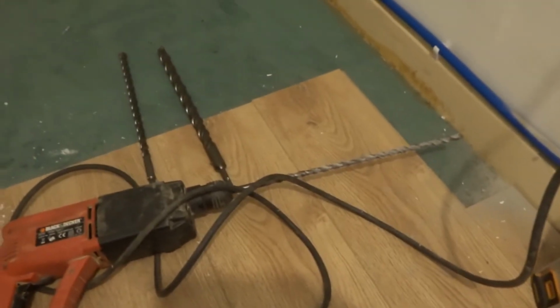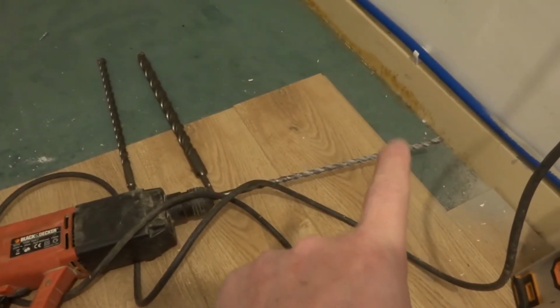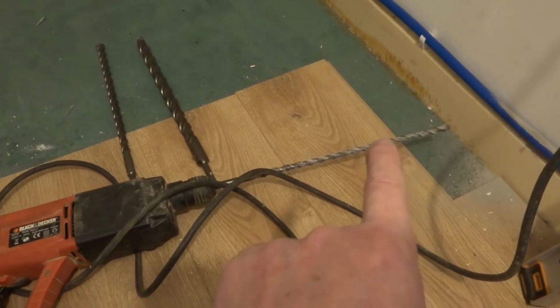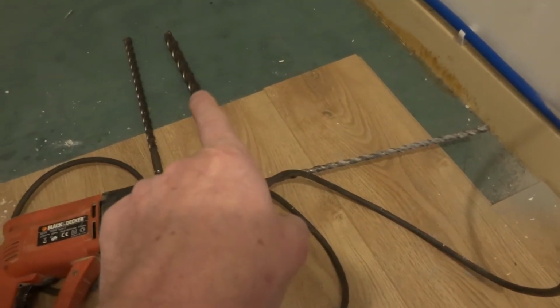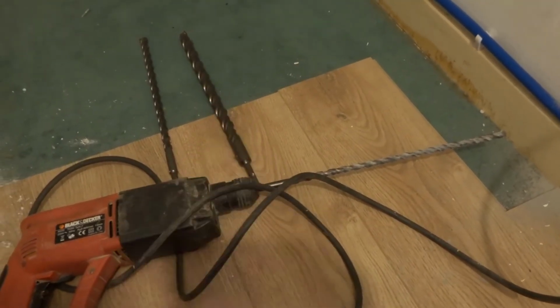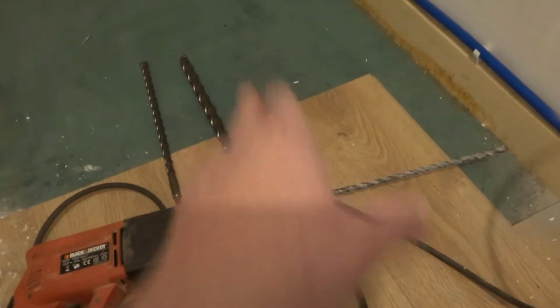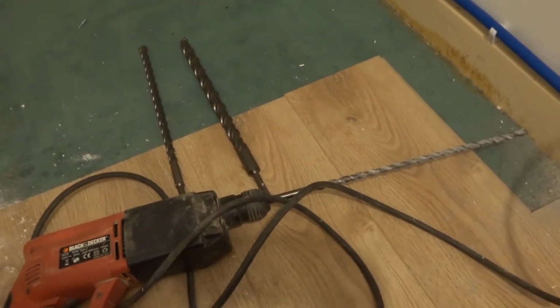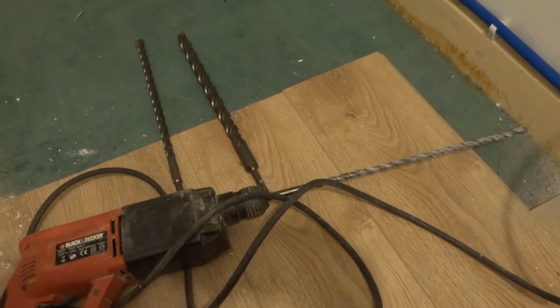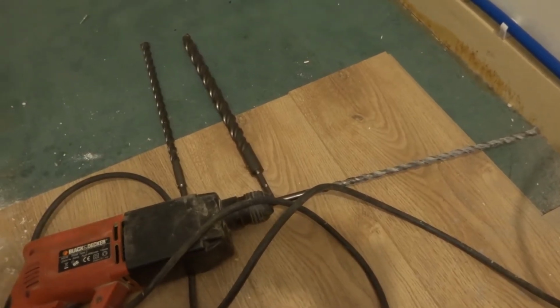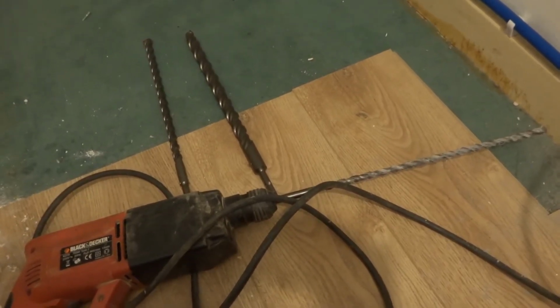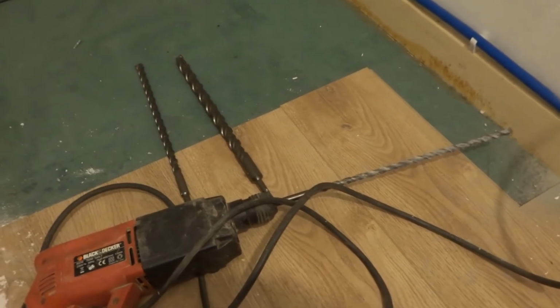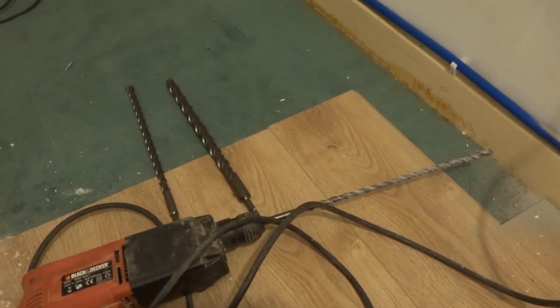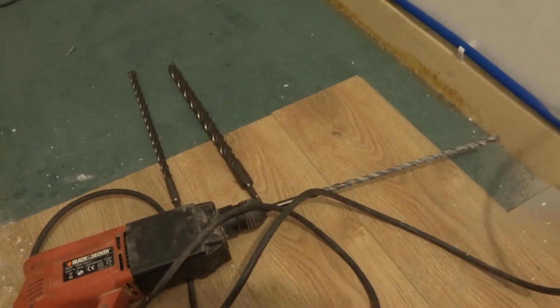I've come prepared, because as it's a double skin wall house I need a big drill and a big drill bit. I'll start with this smaller one, should be a bit easier to get through, and then finish with this 20mm one, because the conduit pipe is 20mm, so I might need to run it around a little in the hole to make the pipe fit. That way I can put a bit of piping in there and the cable won't chafe on the brick, keeping it nice and snug. A little silicone sealant where it comes through each box will make it watertight as well. Okay, let's get on with the drilling.